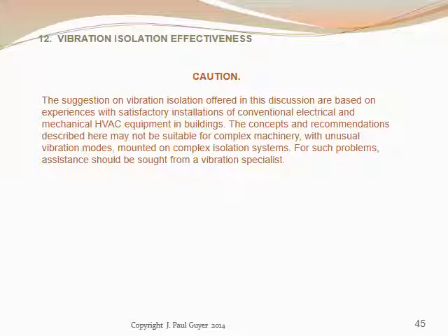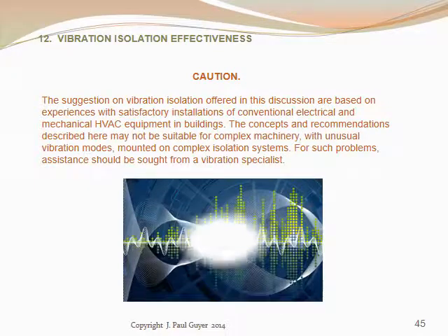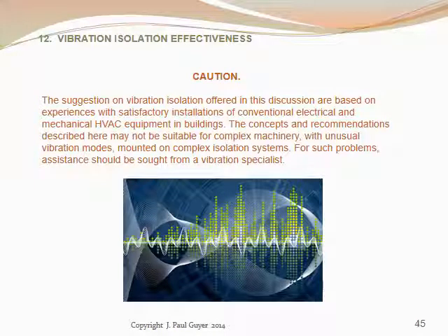Caution: the suggestions on vibration isolation offered in this discussion are based on experiences with satisfactory installations of conventional electrical and mechanical HVAC equipment in buildings. The concepts and recommendations described here may not be suitable for complex machinery with unusual vibration modes mounted on complex isolation systems. For such problems, assistance should be sought from a vibration specialist.